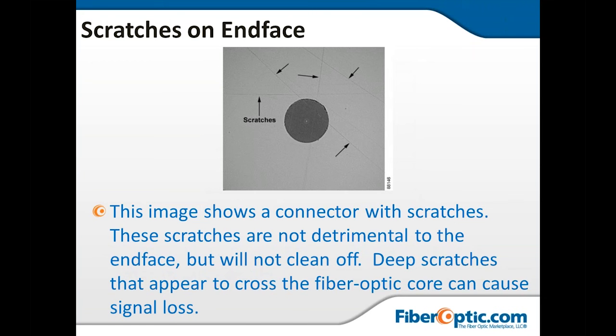Here's a good picture showing scratches through the core, through the cladding, and on the ceramic ferrule end face. This probably is how it was received from the manufacturer, and it somehow got through QC. The good thing is that with a video inspection probe, before hooking it up, the technician caught that there were scratches. That's why with any brand new jumper in a bag, you have to assume something could be wrong with it. You want to inspect it, because otherwise you could put it into the system without looking, cause problems, and then chase your tail trying to figure out where the attenuation is coming from. Inspecting before you connect makes a big difference.